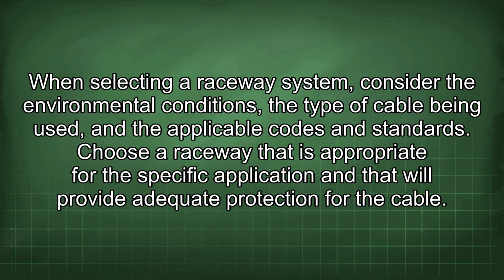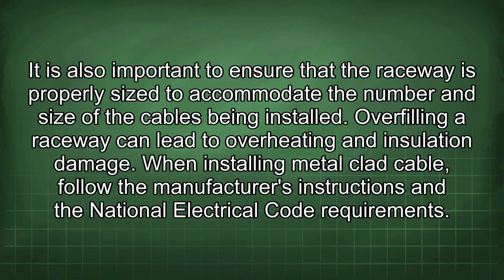When selecting a raceway system, consider the environmental conditions, the type of cable being used, and the applicable codes and standards. Choose a raceway that is appropriate for the specific application and that will provide adequate protection for the cable. It is also important to ensure that the raceway is properly sized to accommodate the number and size of the cables being installed. Overfilling a raceway can lead to overheating and insulation damage.